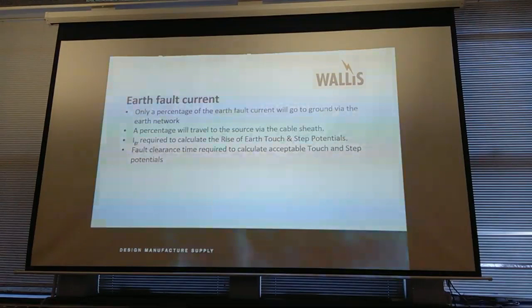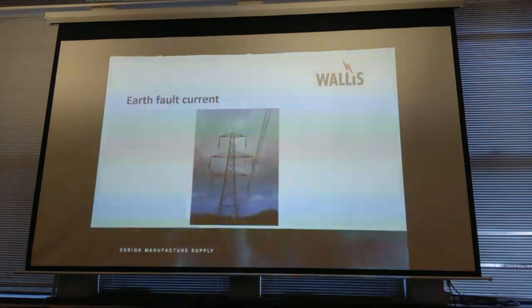Fault clearance times, because again, the human body can withstand more current for a shorter duration and less current for a longer duration. Does that make sense? Right, so again, a little representation there. Standard towers that we have all across the UK, and then that top wire being the shield wire, the earth wire, whatever you want to call it. But that means there is a connection from that tower to that tower to that tower to the substation, both ends, so everything's connected together.